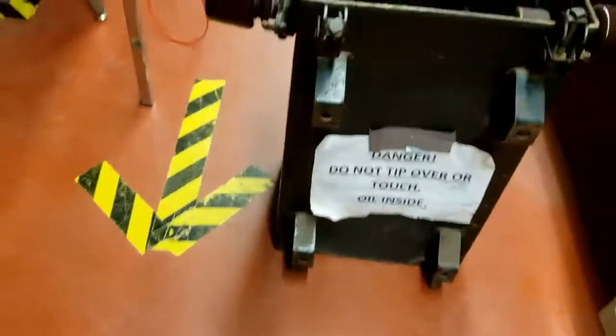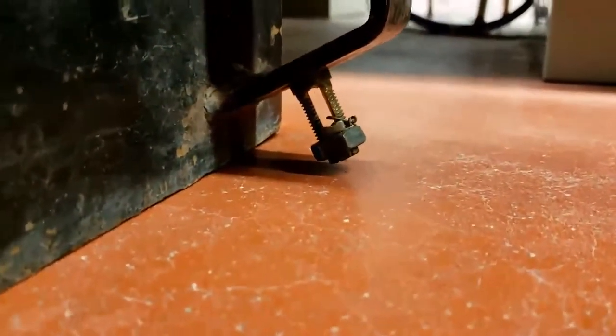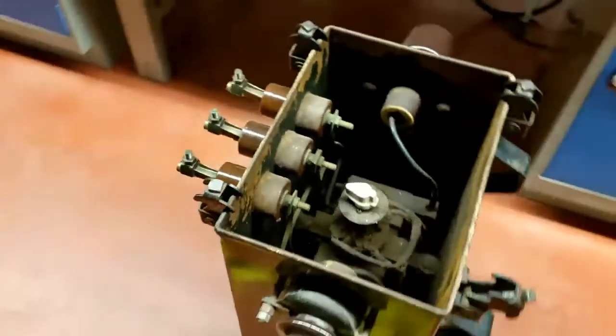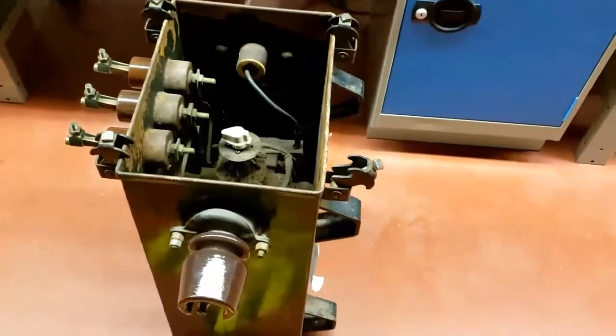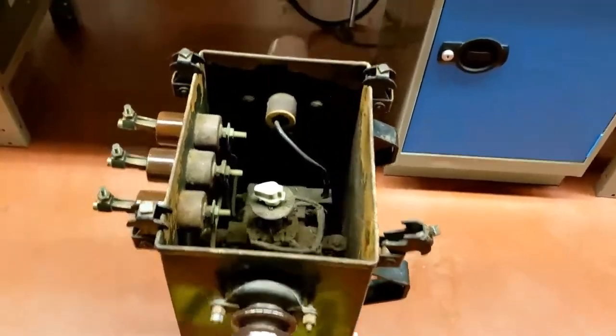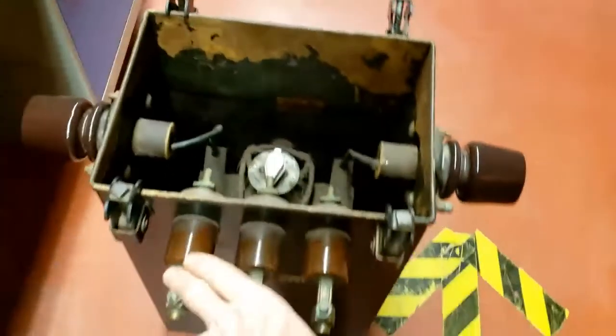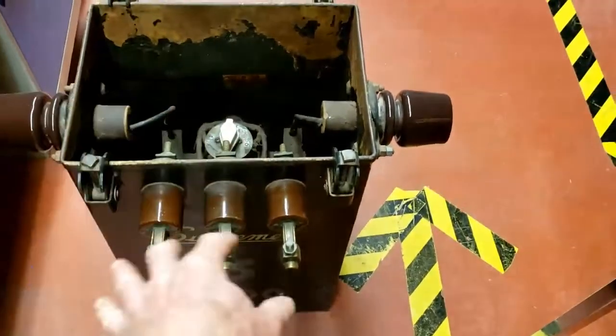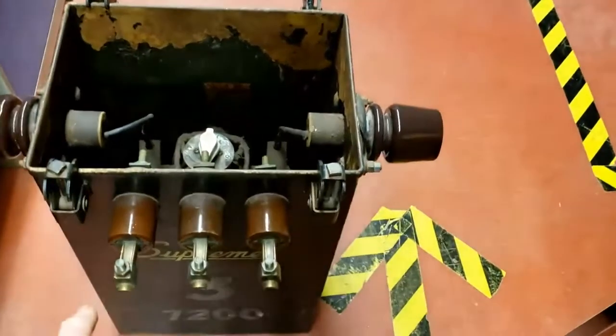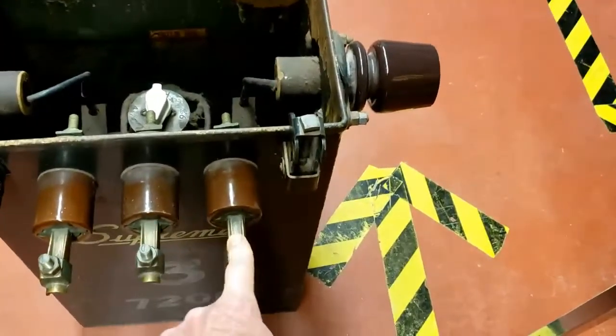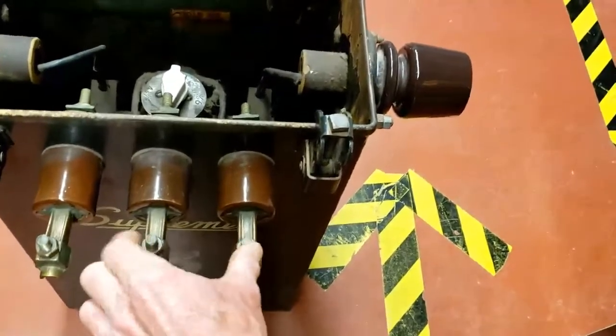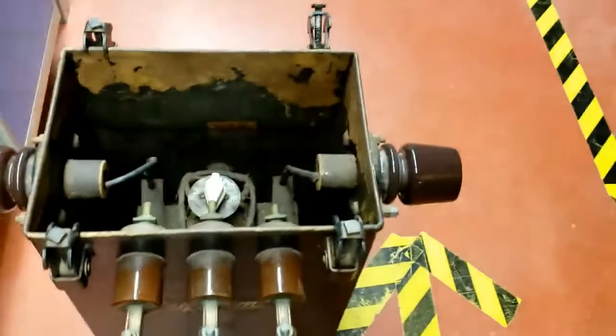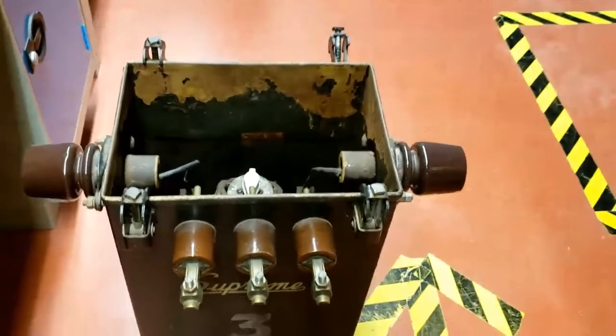When you're doing your measurements on this, there is a ground lug right here that's copper and that's bonded to the case. That will give you your best reading. What you're going to do is follow the lab instructions. You're going to use a multimeter first and measure the resistance of the windings and the secondary, and then the resistance of the primary. You could say this is X0, X1, X2. So you do here to here, here to here, here to here. And then you'd measure the primary just with the ohmmeter, and you can write those readings down.